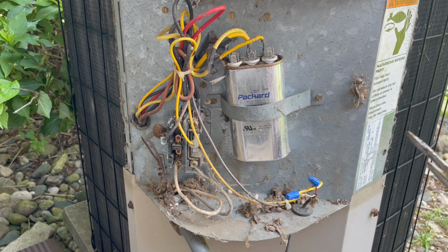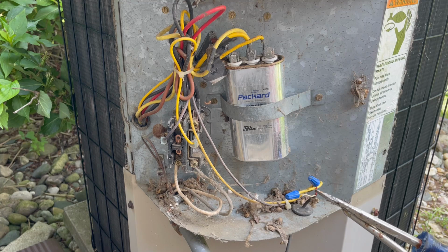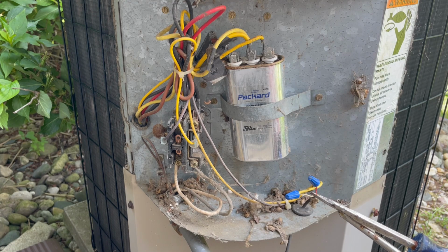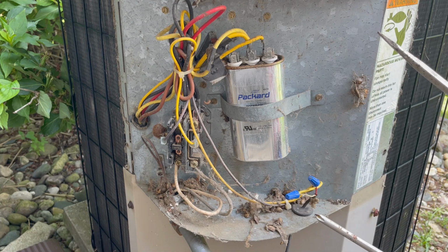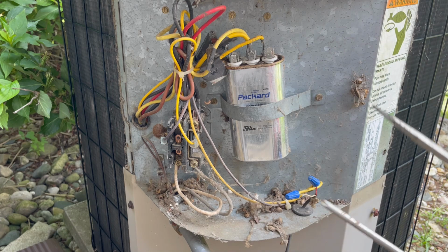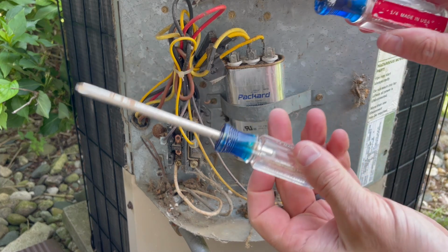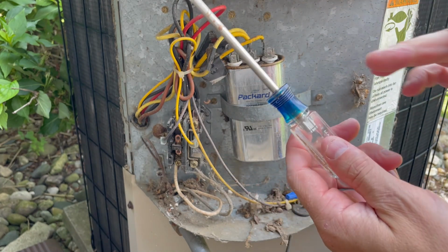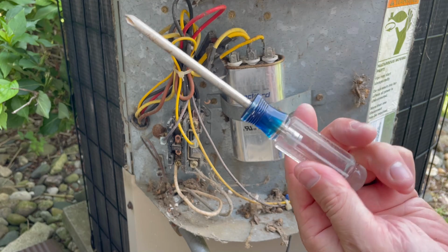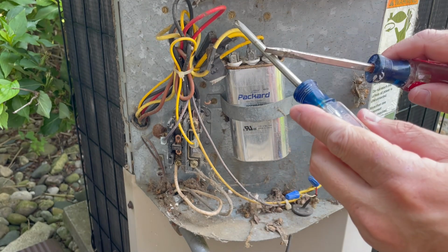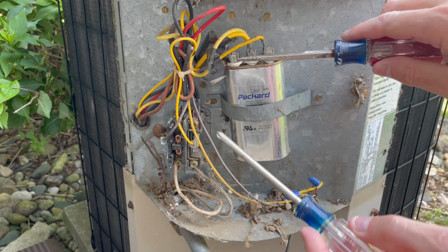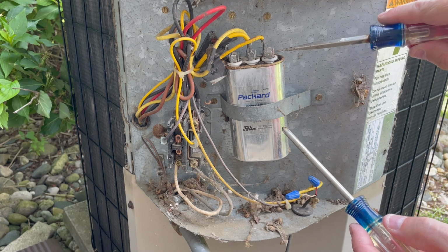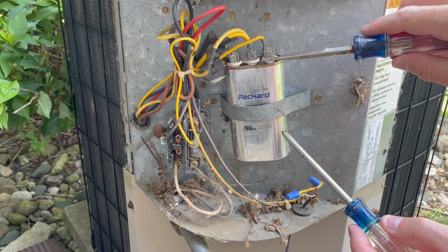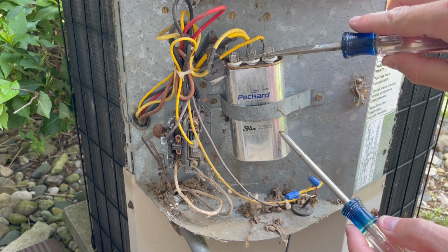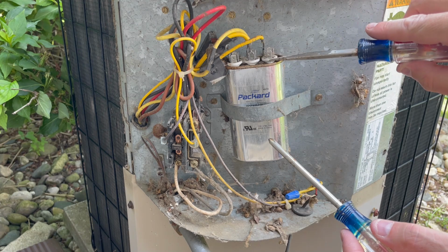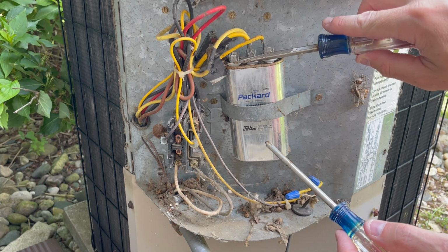There's a few ways to discharge a capacitor. You could use a resistor and some insulated leads to connect it and slowly discharge it. Otherwise, if you've got screwdrivers with rubber or plastic insulated handles, you can use those to touch across the terminals here. We've got our common, and then a fan and a compressor lead.